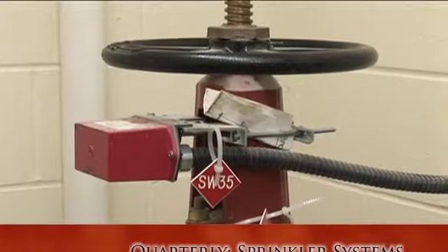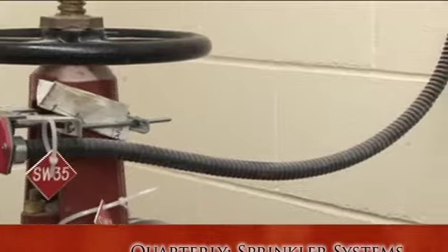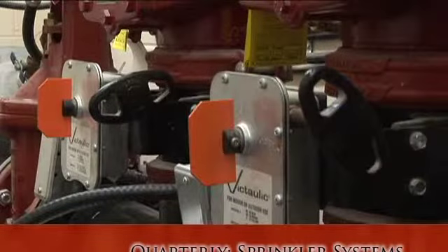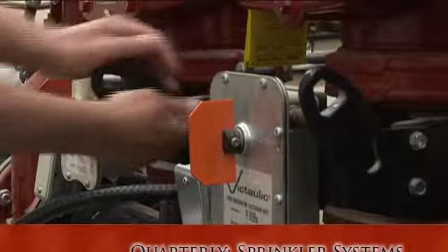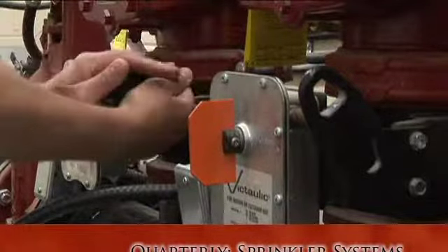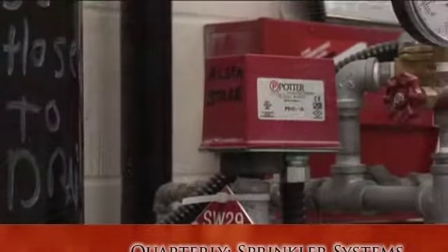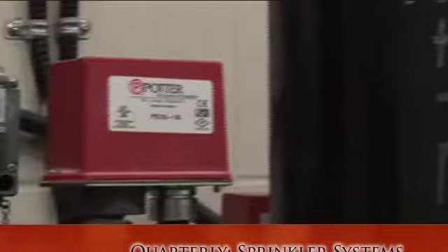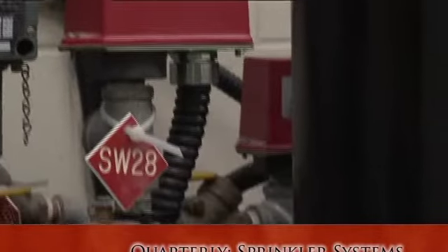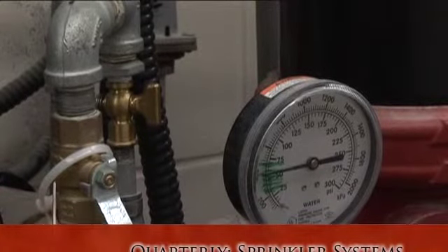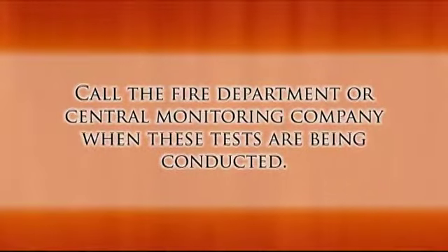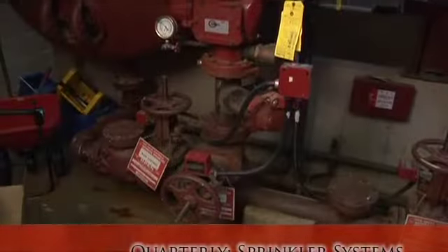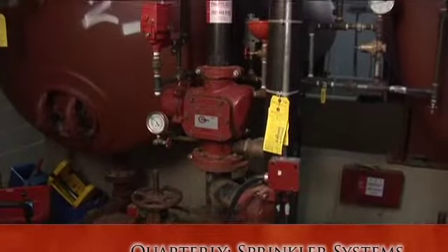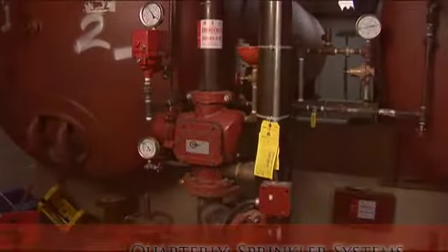Inspect control valves which are electrically supervised to confirm that they're in the fully open position. All tamper switches on sprinkler system control valves need to be tested to ensure that a trouble signal is received at the fire alarm panel should a switch be tampered with. Now, test all sprinkler water flow activating devices by flowing water from the test and drain valve to confirm that the signal is also received at the fire alarm panel. Before conducting these tests for both items 2 and 3, make sure that the fire department or central station monitoring your fire alarm system has been notified that testing is being conducted. Now, if applicable, inspect your dry pipe valves to ensure that the priming water is maintained at a proper level.